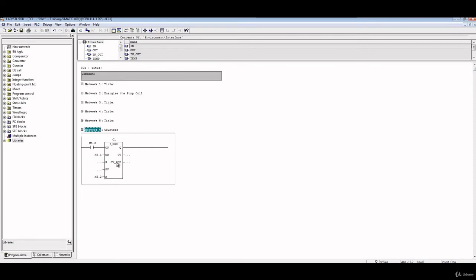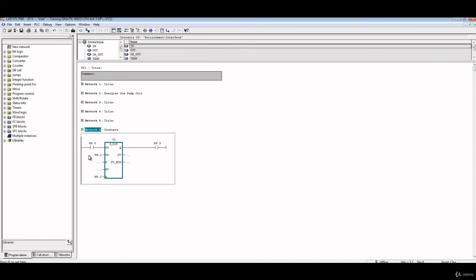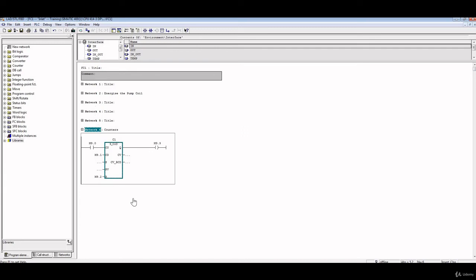I'll put here Q, a value of M9.3. So what does that mean? If M9.0 changes from 0 to 1, the CV here will be one. If another change happens, it will be two. Another change happens, it will be three. If another change happens on M9.1 from 0 to 1, CV will be decremented from a value of three to a value of two, and then a value of one and so on. If M9.2 equals one, the value here of CV will be zero.